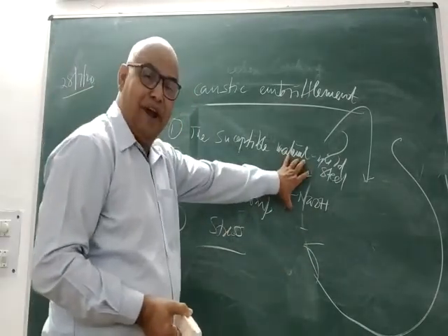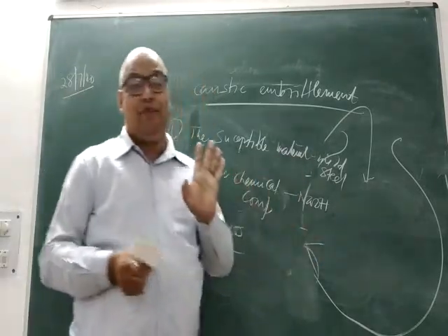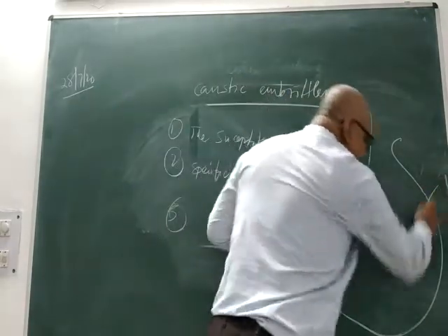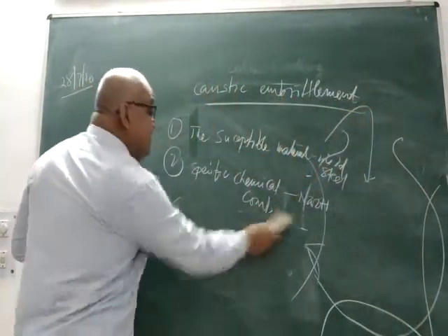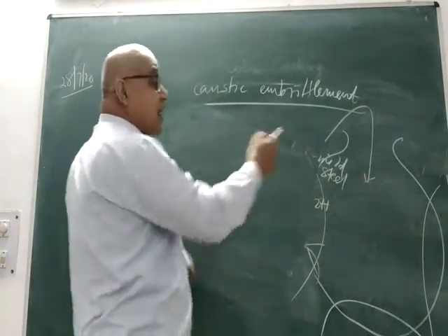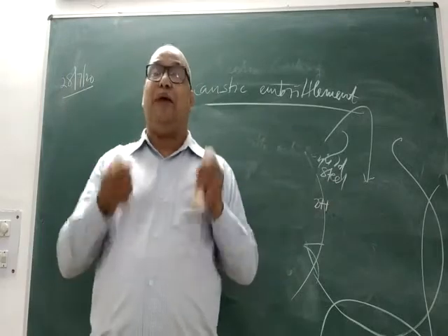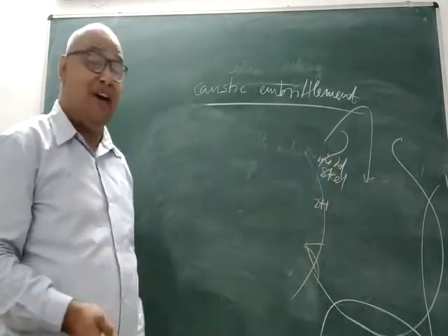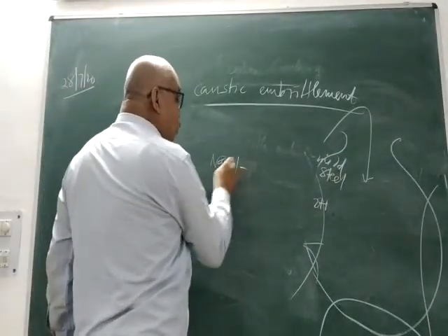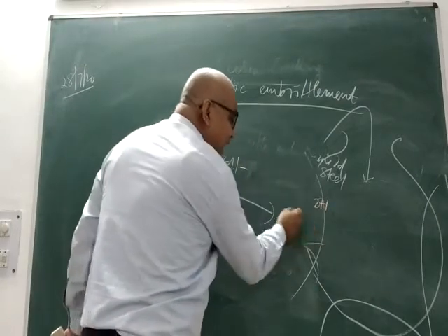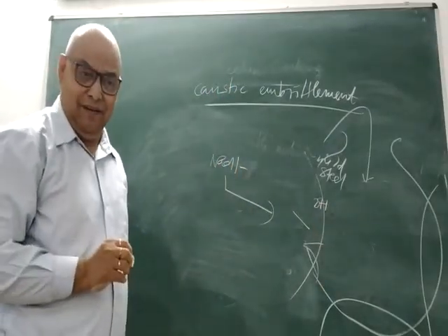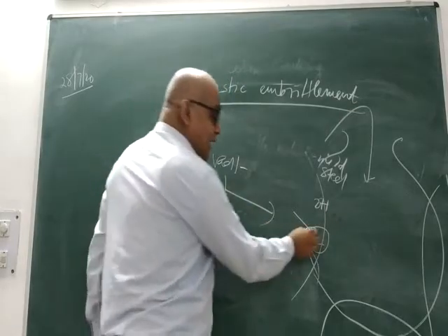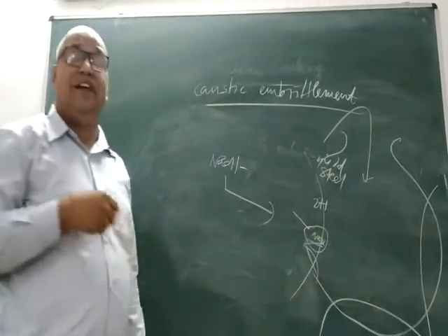The two points are satisfied, and if there is any stress, I have told you, where there will be a possibility of stress: bend, joint, and there are bends in the boiler. And therefore, there is every possibility that there are hairline cracks, which cannot be seen by the open eye. And if any kind of hairline crack is there in the boiler from inside, this sodium hydroxide will infiltrate into the crack by capillary action.